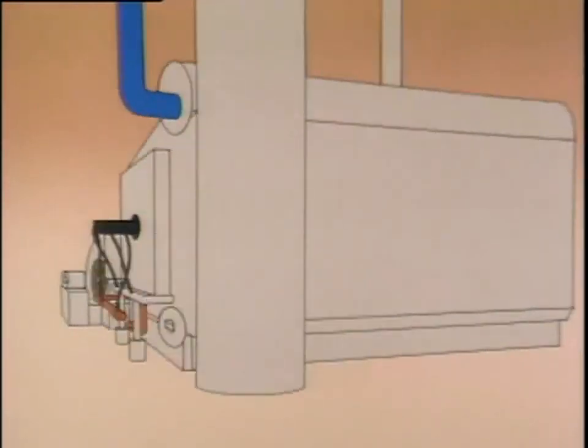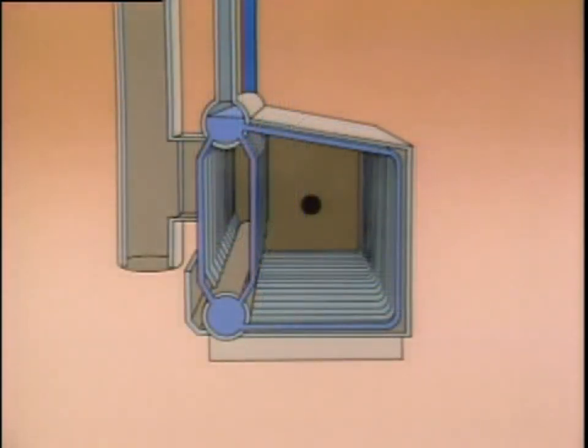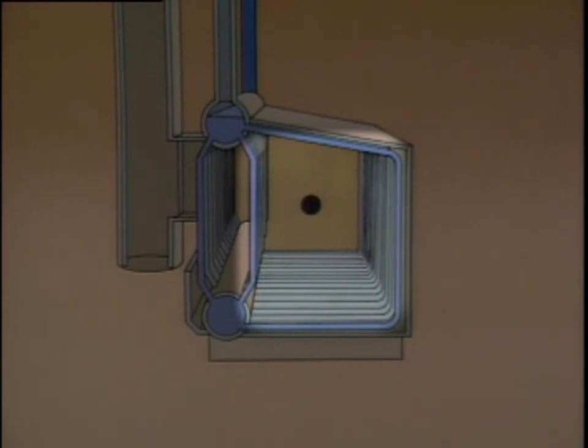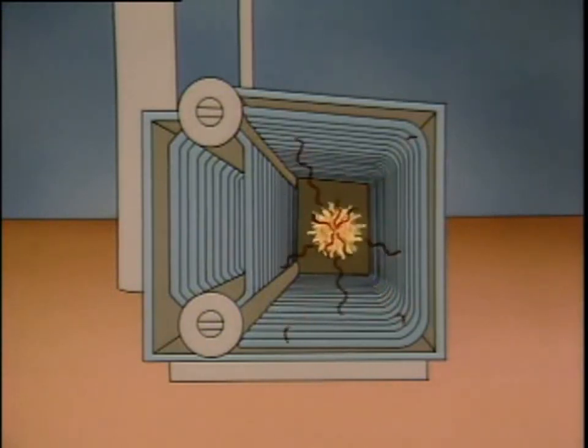We've now seen the principles behind radiation, convection, and conduction. Each of these types is involved in transferring heat from the burning fuel to the water in a boiler. This type of boiler is called a water tube boiler, but the heat transfer principles at work apply to just about all boilers. The boiler has a series of tubes and two drums which distribute water to the tubes. The tubes form a wall around the combustion area — the area where heat is generated. When fuel burns in a boiler, radiant energy in the form of electromagnetic waves is produced. These waves travel through the combustion area, and the waves in a direct line of sight with the tubes make contact with the outer tube surfaces, and the tubes absorb heat. This is radiant heat transfer.